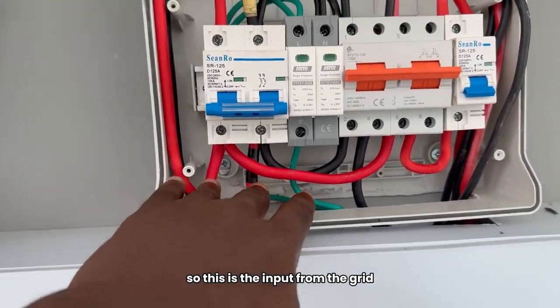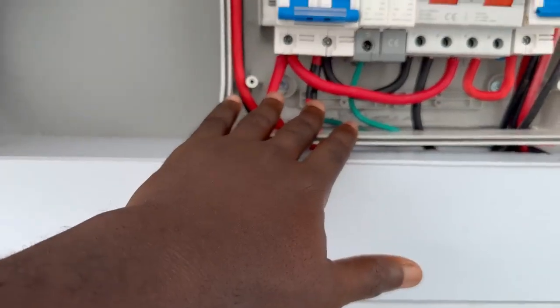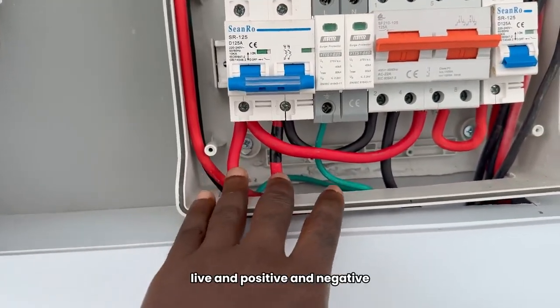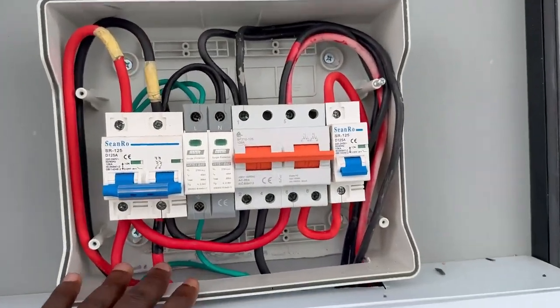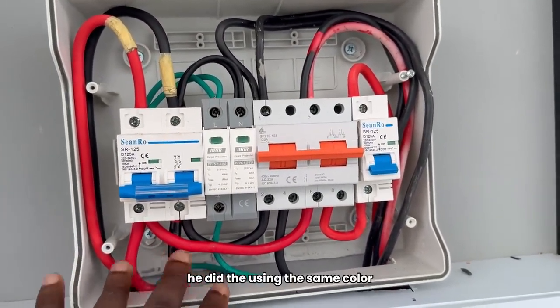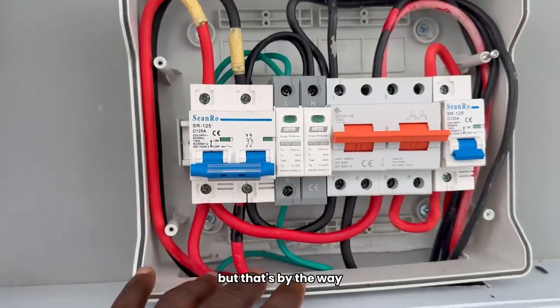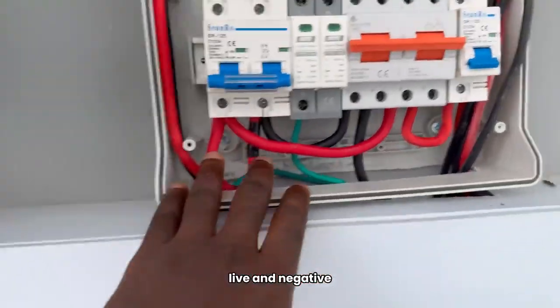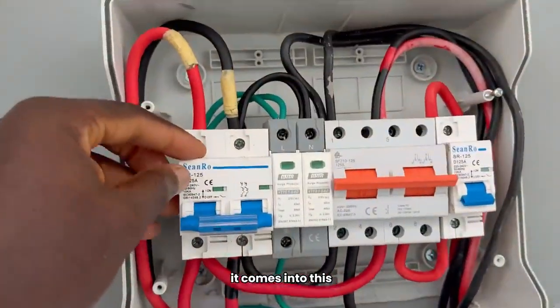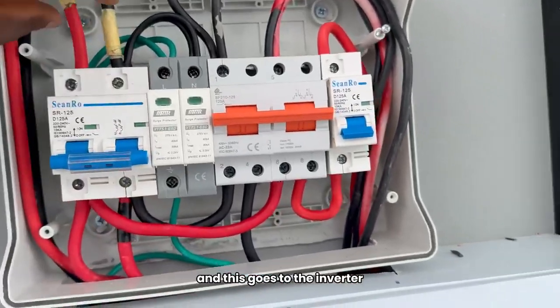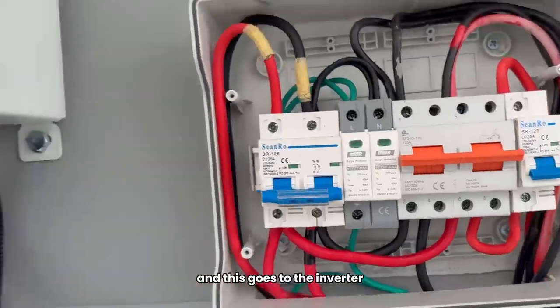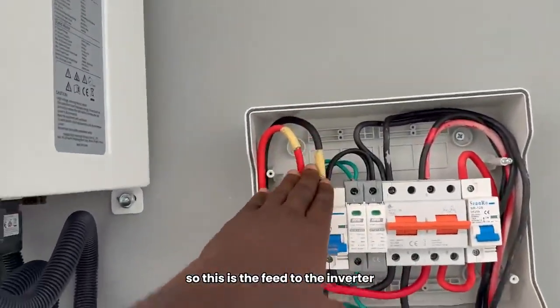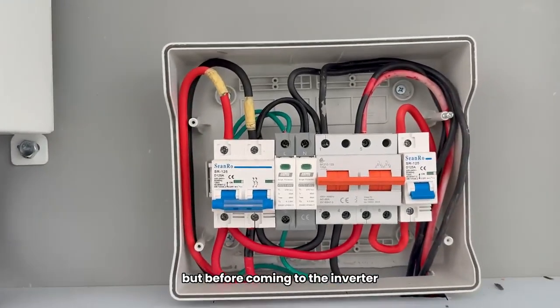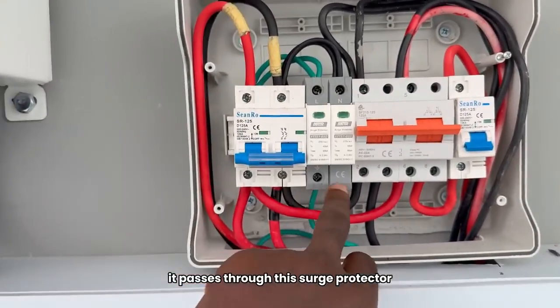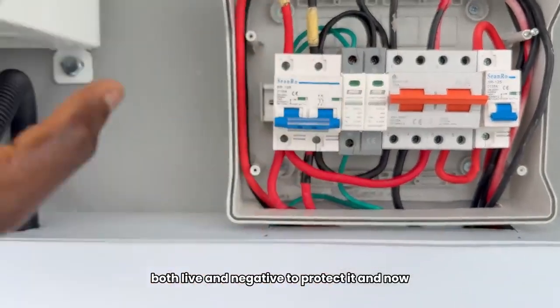This is the input from the grid, NEPA, live and positive and negative. Like I said, the electrician who wired it just grabbed the cable for us, so he used the same color, but that's by the way. Live and negative come into this 125 amp breaker, and this goes to the inverter. But before reaching the inverter, it passes through this surge protector, both live and negative, to protect it.